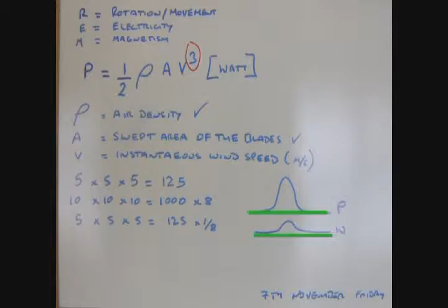What I spotted all those years ago is that we could add a step into the control loop, PS for power station, and instead of that lovely flat line occurring at 335 kilowatts, we could make it happen at 200 kilowatts, 150, 120, and I've had it all the way down to 10 kilowatts. That means you flat line your wind resource. You have time on this axis, power on that one. So all our diesels see when we're flat lining is that people have switched power off. The diesels take the normal variations they would anyway, and they're perfectly happy—they don't have to deal with the volatile nature of the turbine.